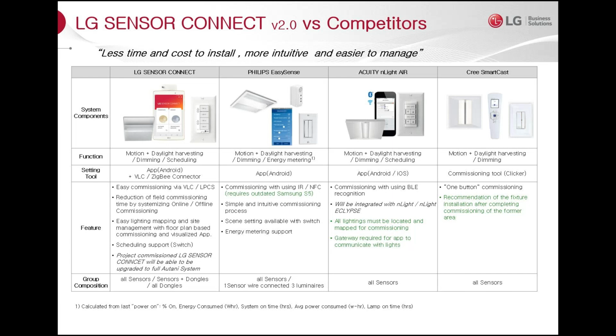However, it means more work for the installers. You have an external component called a gateway or a lighting panel that your Android or iOS device connects to, and that works as a bridge. Your phone has to be connected to this gateway in order to talk to the lights, because the gateway then converts your communication over to Zigbee or whatever components they're using. Your phone is never actually directly connected with the lights. So what that means is if that gateway or lighting panel shuts down, you have no communication with the lights.